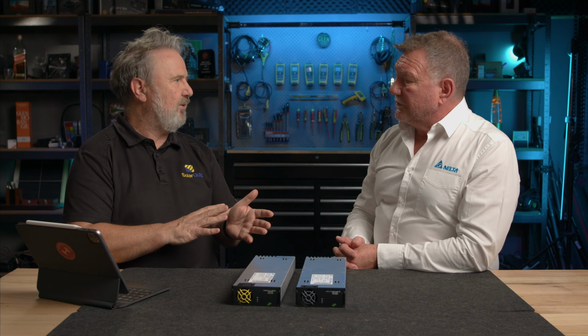But if you're not in one of those harsh environments, a fan filter type arrangement works just as well, in fact it actually works better. It's exchanging air with the outside atmosphere through a filter, so there's a little bit of maintenance on that filter over time depending on the dust, but it's quieter and more efficient at cooling. The controller will tell you when that filter needs to be looked at, so it looks after you.